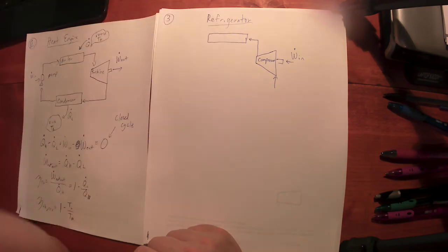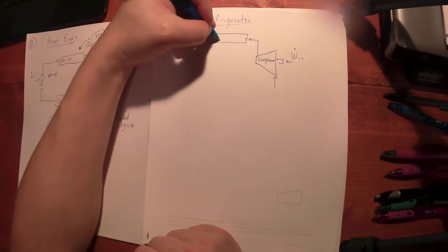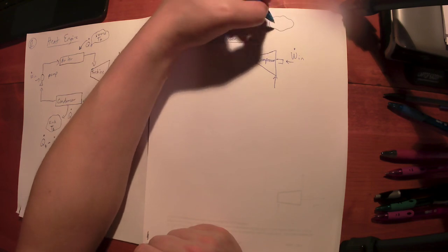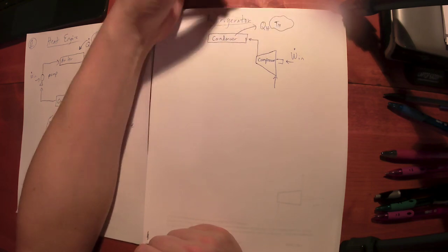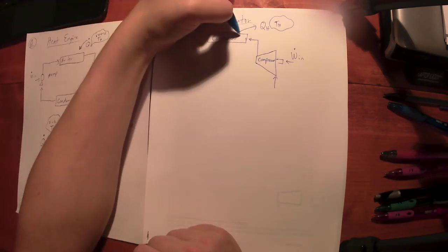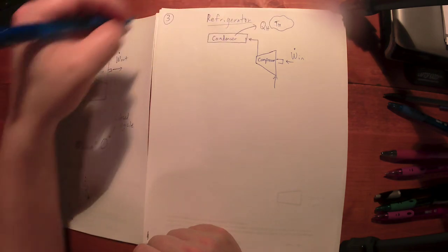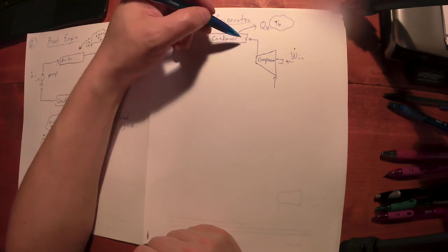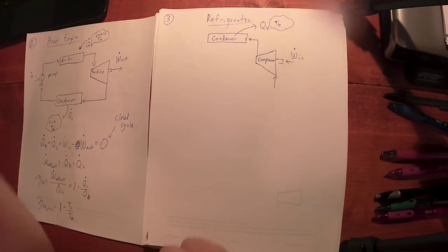So the idea in the compressor is you want to get the fluid, the refrigerant in here so hot, get it screaming hot, I like to say. Get it so hot that when we run it to the high side coils, the condenser coils, it will actually lose heat to a high temperature reservoir, the outside air, if you will. If we're trying to refrigerate the air inside a space, you want to reject heat to the higher temperature outside air. So the goal is to get the refrigerant in the compressor, by squeezing it and adding energy to it, so hot that it'll lose heat to the higher temperature source.